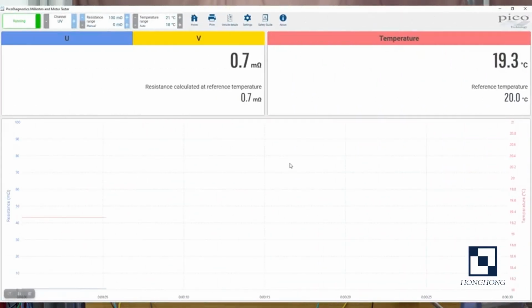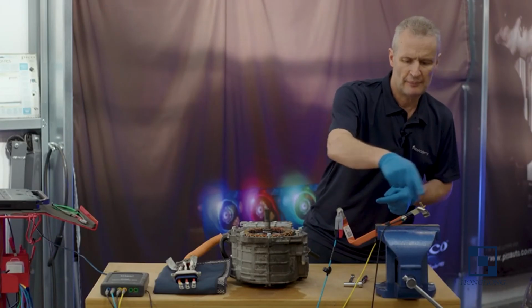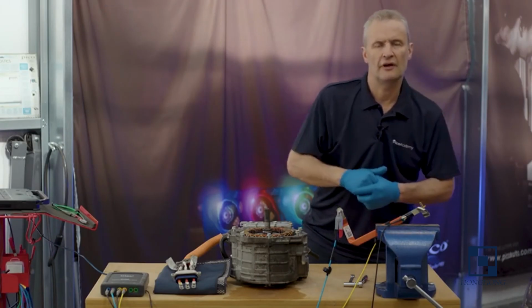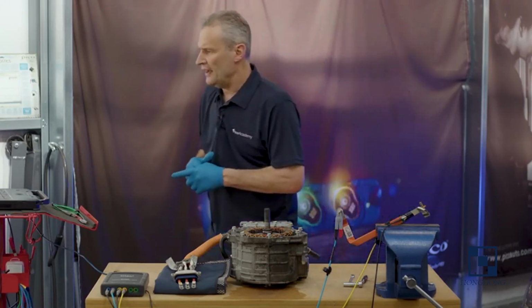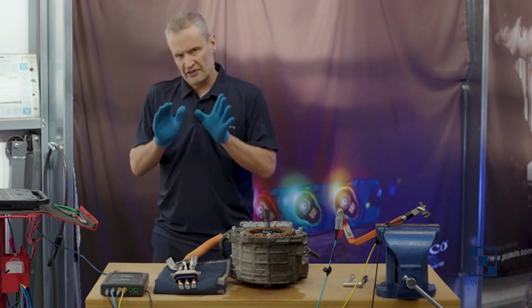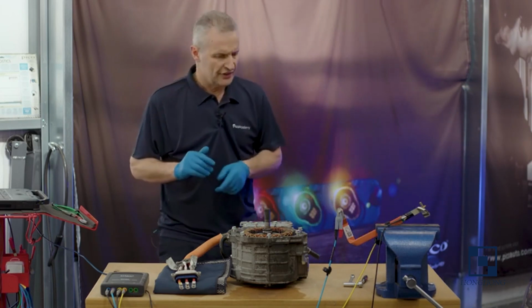Notice the temperature. I've moved the temperature probe from the motor now, and I've attached it to the bus bar because we're able to compensate for temperature. Now, the blue line, of course, is resistance, and the red line is temperature in the graph.